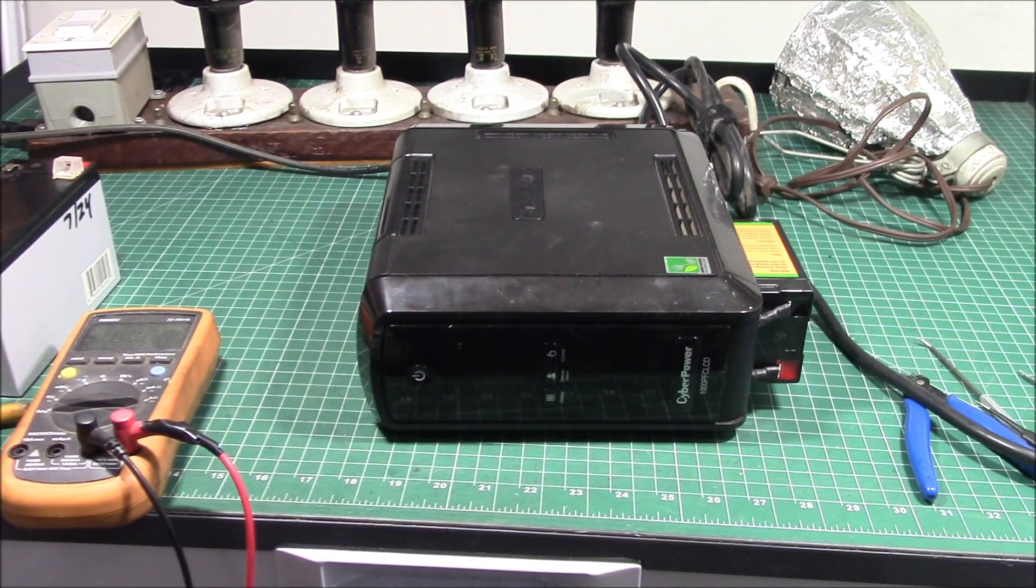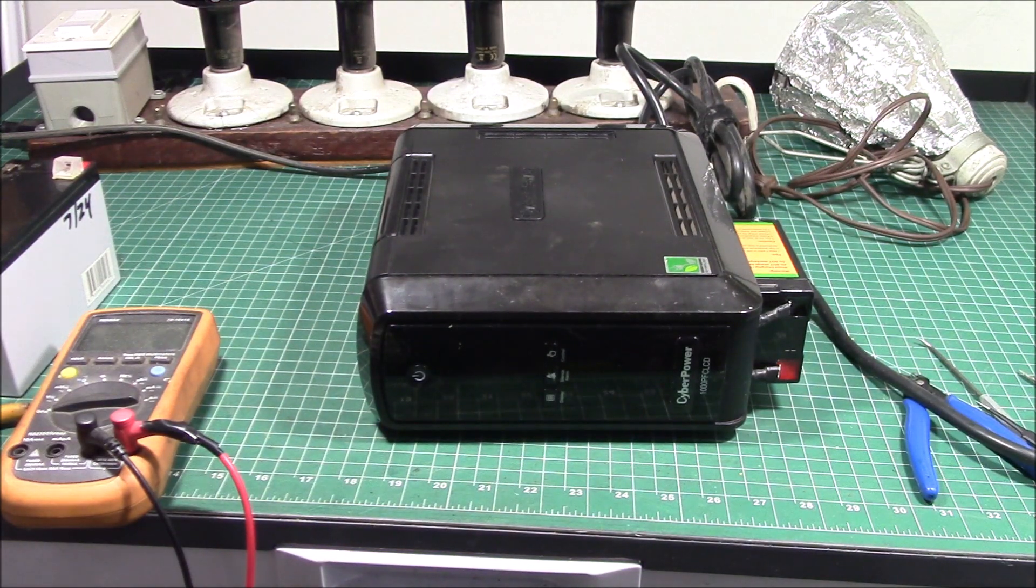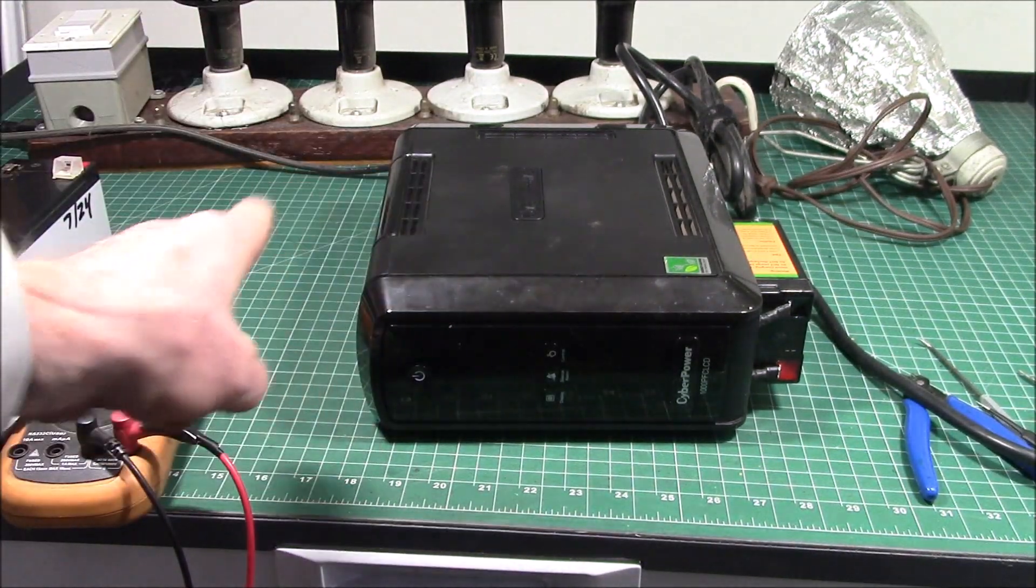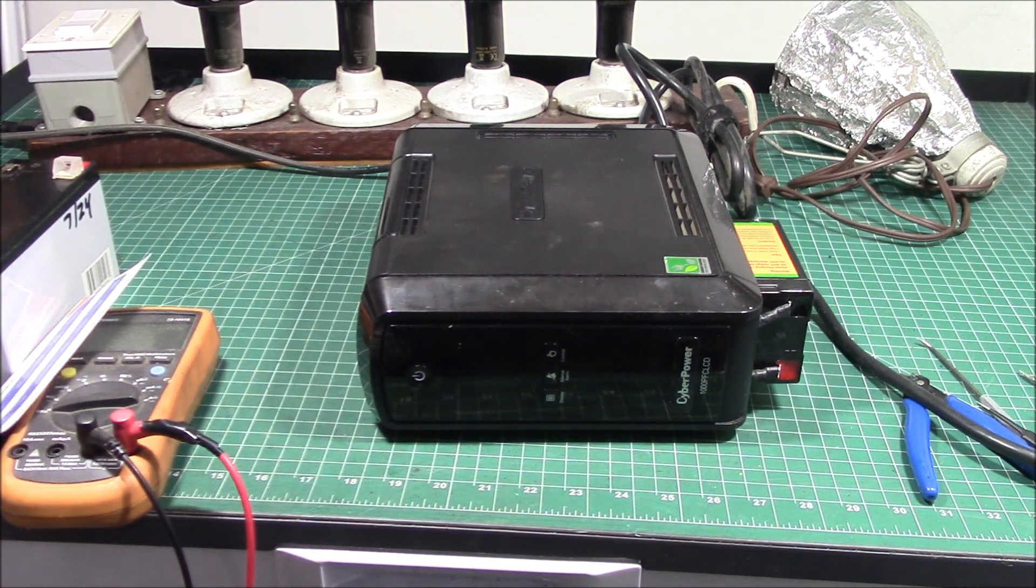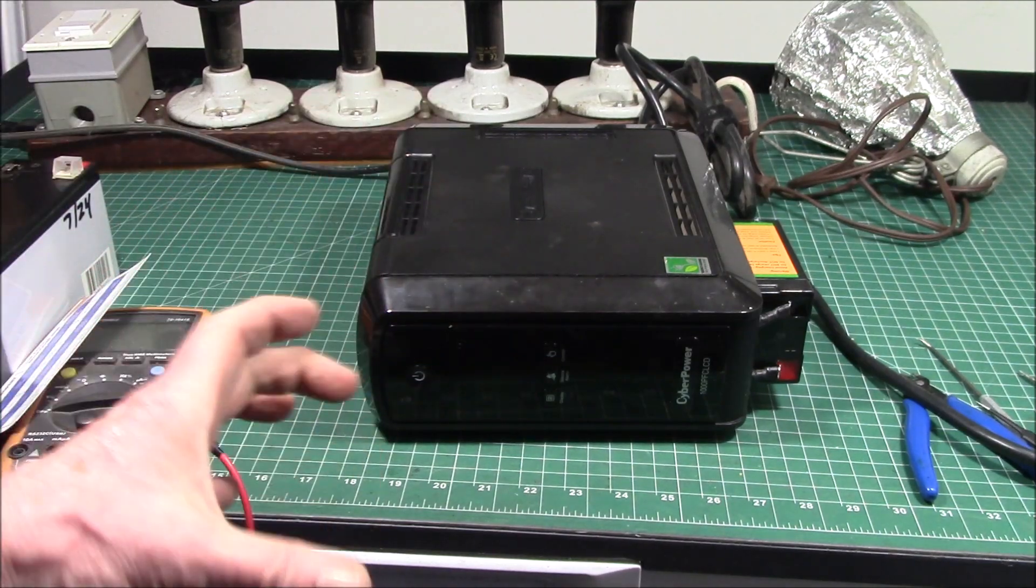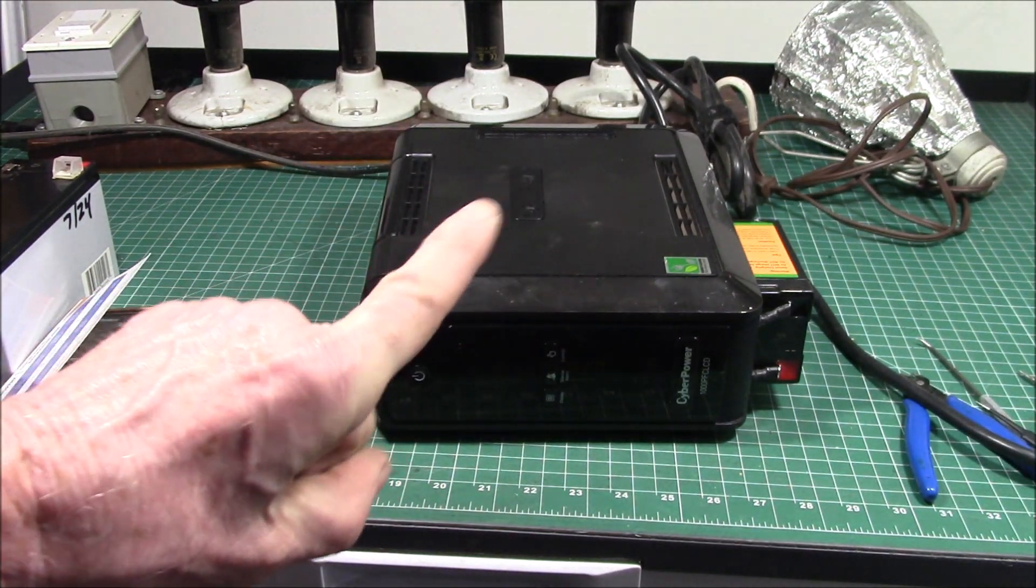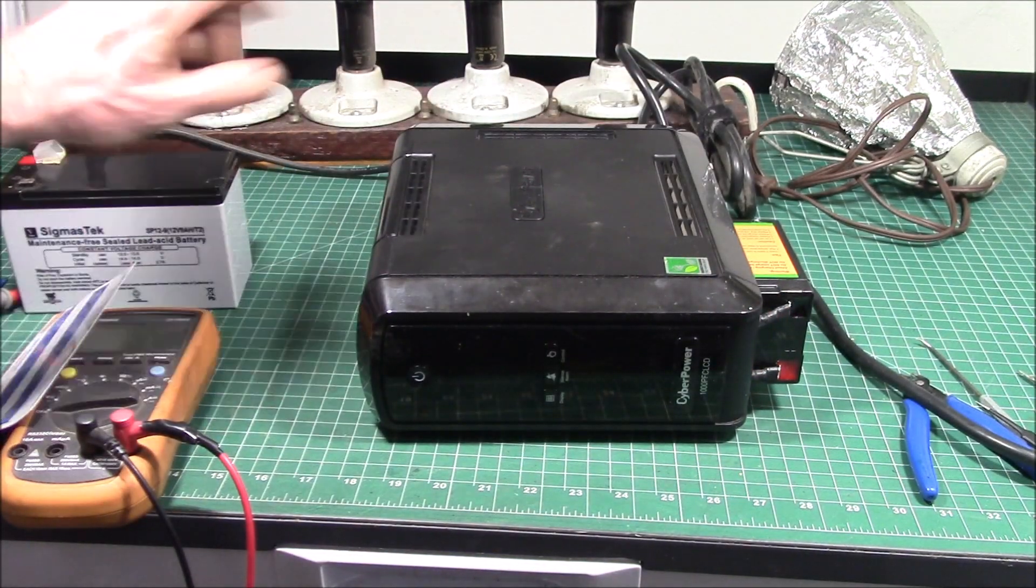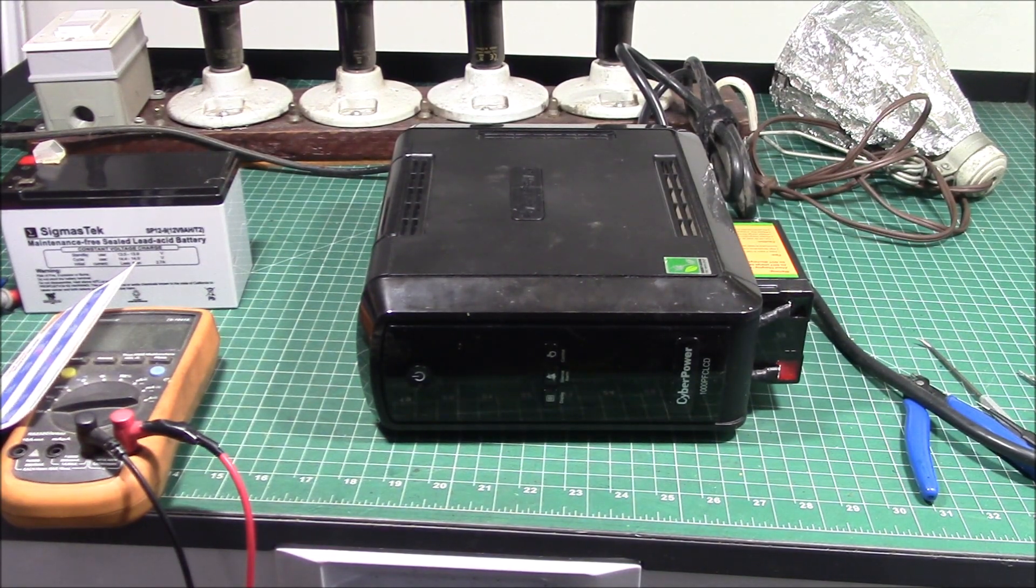I think the BMS inside that lithium iron phosphate battery, just like it says here, peak current 33 amps for 10 seconds, and that's about, you know, at 300 watts with the conversion and everything, that's probably 30-some amps at 12 volts. The listing for the battery says UPS and it even says CyberPower, so it's physically the right size and it's the right volts and amp hour rating. In fact, it's one amp hour better than the lead-acid - this was nine amp hours, that one is 10. So on paper you would say this is a better battery, but it's only good for 30 amps or roughly 300 watts.